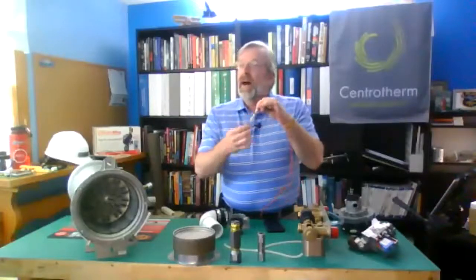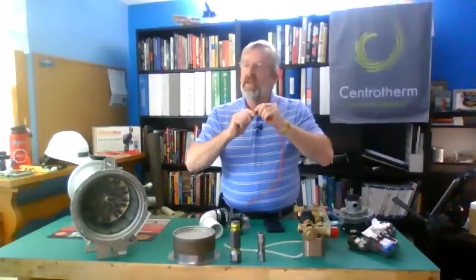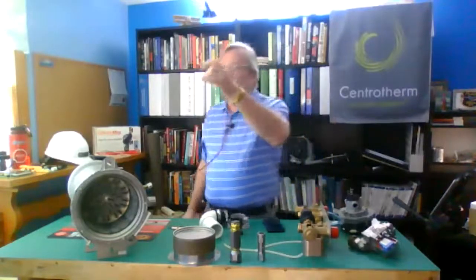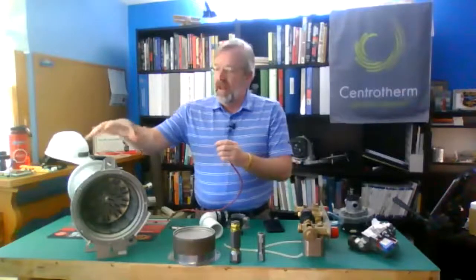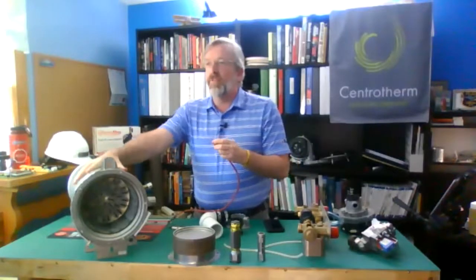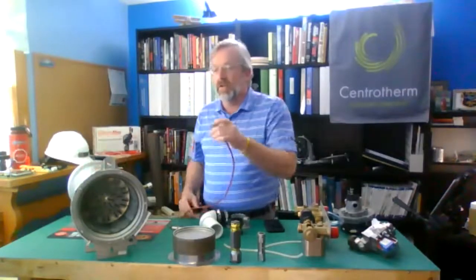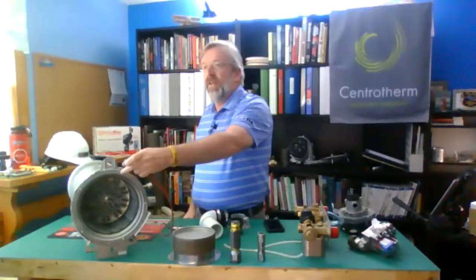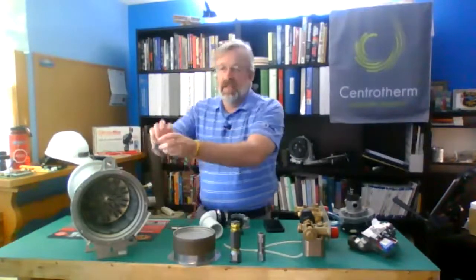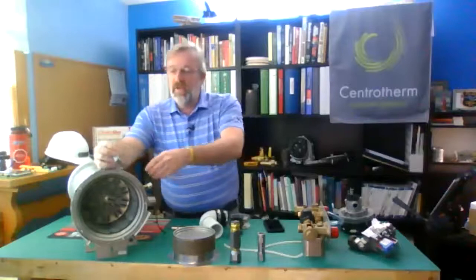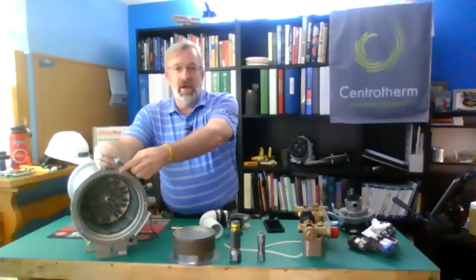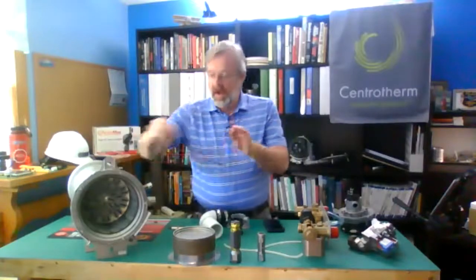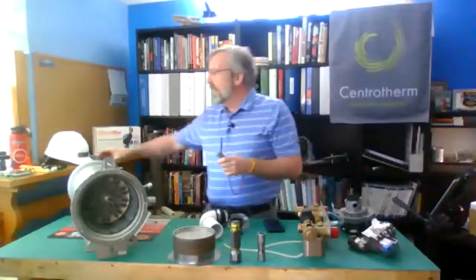But if I don't get spark here, disconnect it from there. Now at this point in time, what we're going to do is we need to get to ground. Now, if you think about it, the heat exchangers are just a big chassis ground because we're grounded to everything. Hold it off one of the studs on the heat exchanger there. And what you do is let it spark from here to here. If I'm not getting spark there to there, I didn't get spark here. Let's keep working our way back.